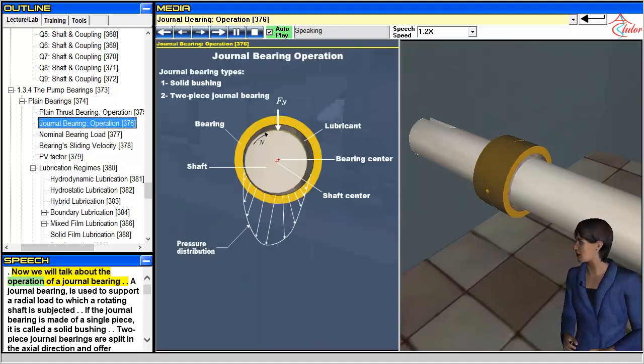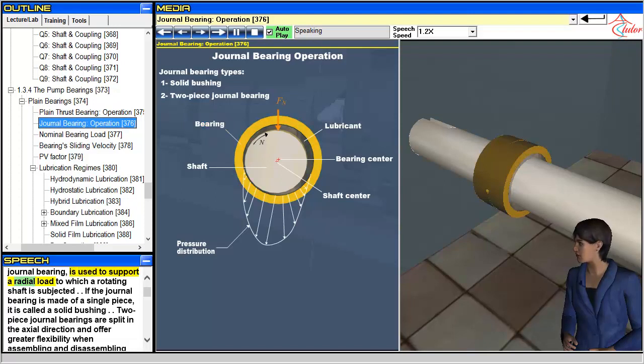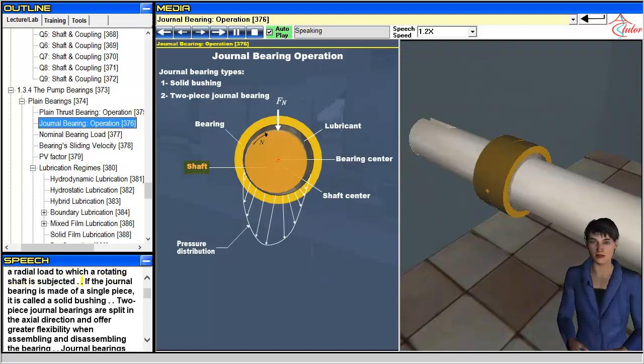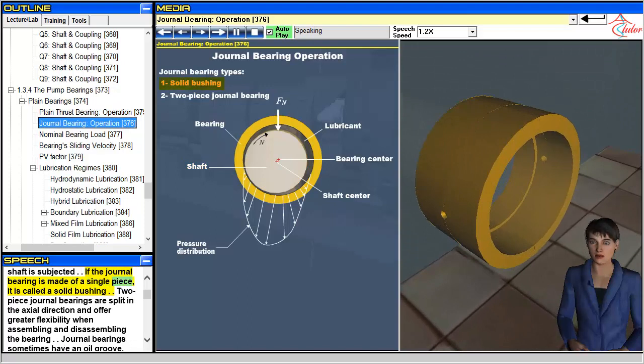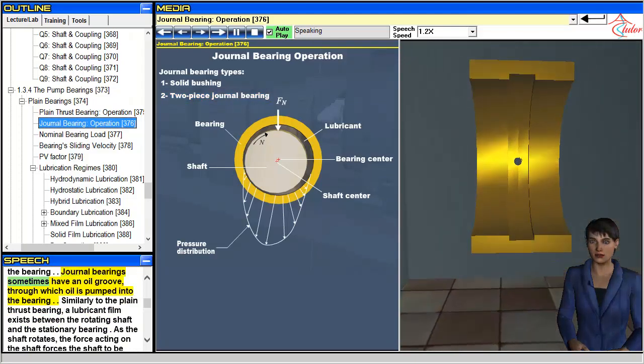Now we will talk about the operation of a journal bearing. A journal bearing is used to support a radial load to which a rotating shaft is subjected. If the journal bearing is made of a single piece, it is called a solid bushing. Two-piece journal bearings are split in the axial direction and offer greater flexibility when assembling and disassembling the bearing. Journal bearings sometimes have an oil groove through which oil is pumped into the bearing.